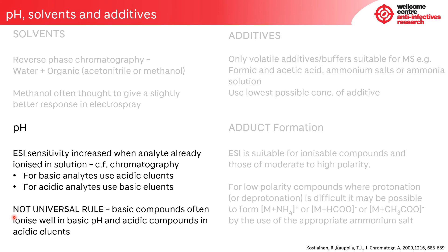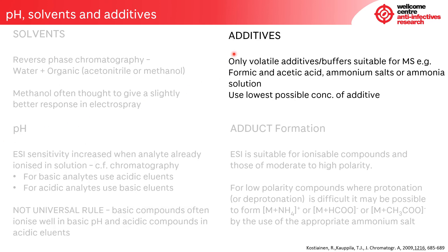One thing to be aware of is that while compounds ionized in solution may give a better mass spec response, it may prove problematic in terms of the chromatography. Only volatile additives or buffers are suitable for mass spectrometry, such as formic and acetic acid, or ammonium salts or ammonia solution. Generally you should use the lowest possible concentration of additive you can get away with, and there's typically a trade-off between the mass spec response and the chromatographic response.